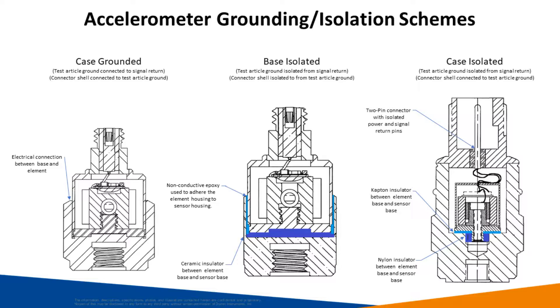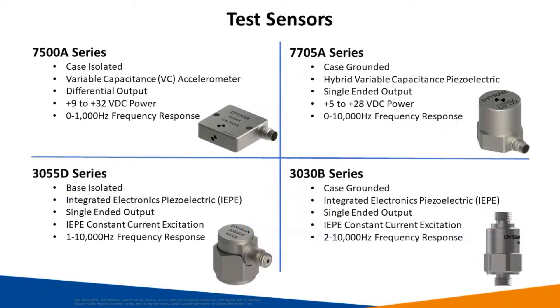The second type are base isolated sensors. These are sensors that use hard anodized cups or washers and base assemblies constructed with non-conductive epoxy. These methods isolate the mounting surface of the sensor from the test article. The third type are case isolated sensors. These are sensors that are isolated within the sensor's housing and utilize multi-pin connectors to isolate the ground return from the entire sensor housing and connector shell.